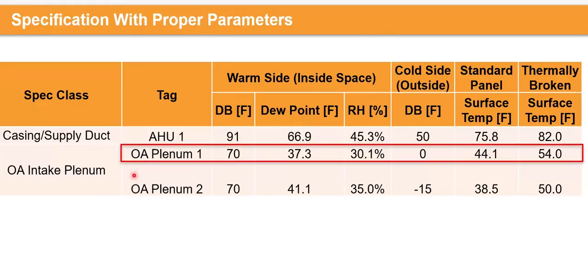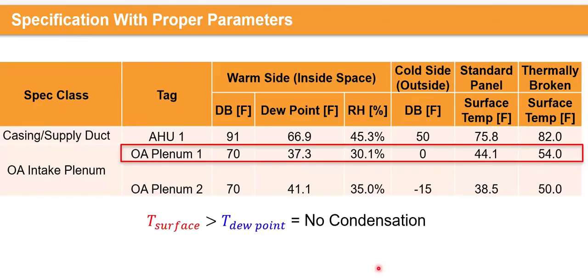Once you have a look at your outside air plenum, you do have much colder air coming in. And with a relative humidity of 30 percent, you also have a dew point of 37 degrees Fahrenheit. The standard panel, again, does a good job at that point because it is about 7 degrees above the dew point, so there is no condensation. The thermally broken still does an excellent job in this. So no condensation so far, and we are all happy.